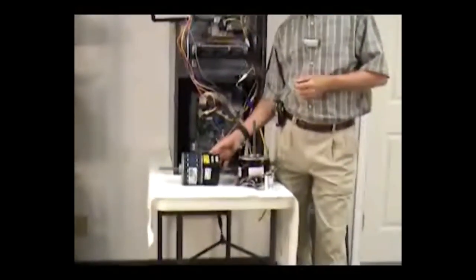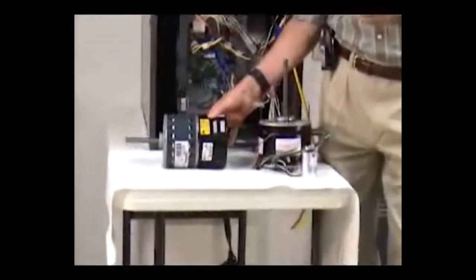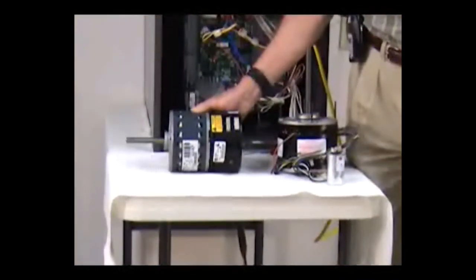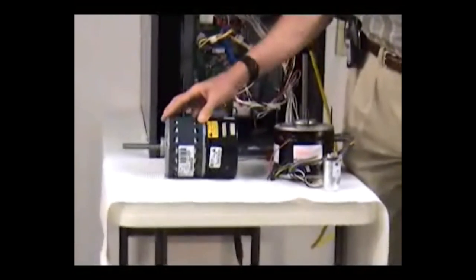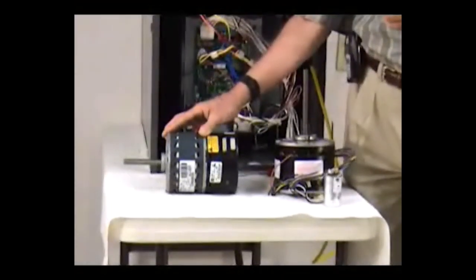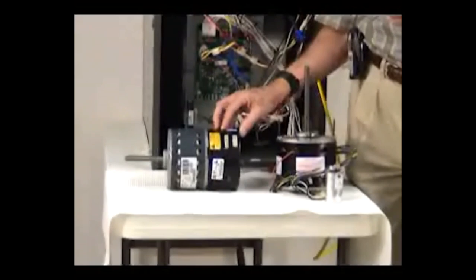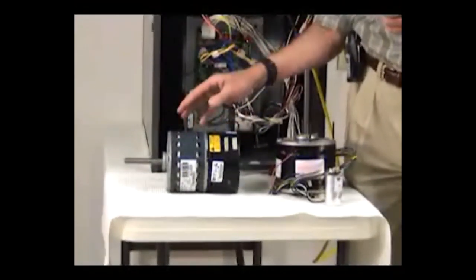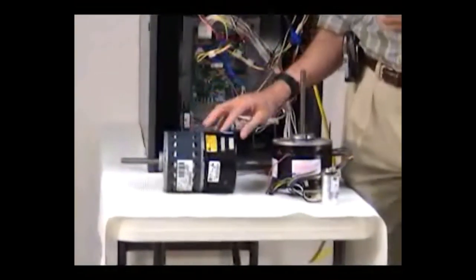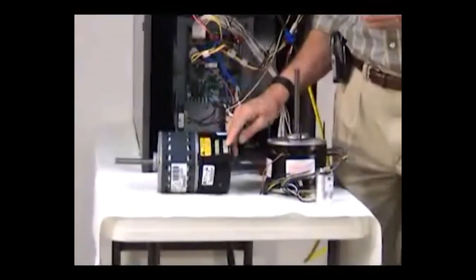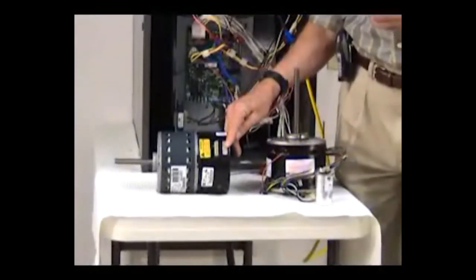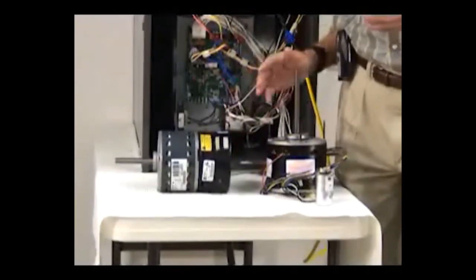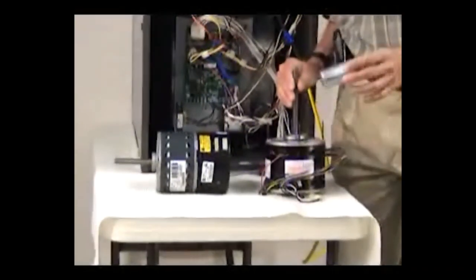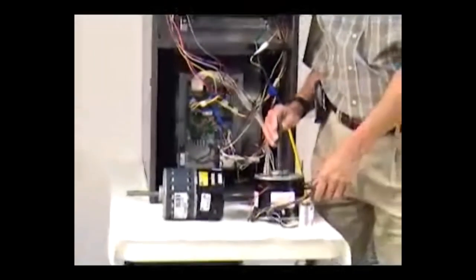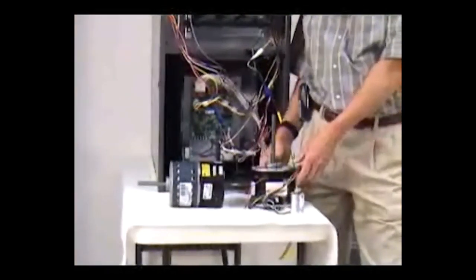Basic difference between the two motors, as a review of what we've just gone through, is we have a module attached to the back of our ECM motor. The ECM motor itself is a DC motor. We're giving it AC supply to the module, DC to the motor itself. 115 or 230 volt applicable, with 24 volt signals supplied to the module itself.